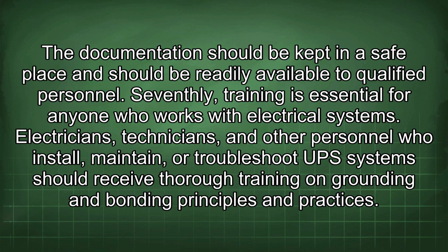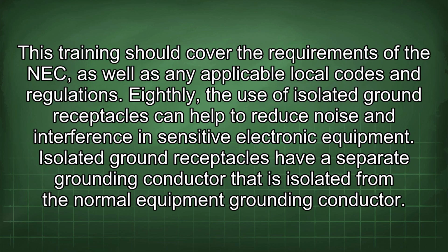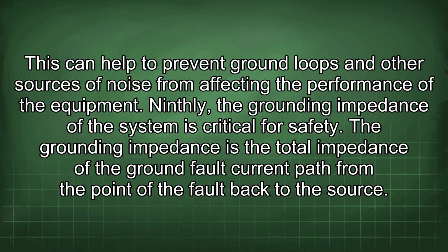The electricians, technicians, and other personnel who install, maintain, or troubleshoot UPS systems should receive thorough training on grounding and bonding principles and practices. This training should cover the requirements of the NEC as well as any applicable local codes and regulations. Eighthly, the use of isolated ground receptacles can help to reduce noise and interference in sensitive electronic equipment. Isolated ground receptacles have a separate grounding conductor that is isolated from the normal equipment grounding conductor. This can help to prevent ground loops and other sources of noise from affecting the performance of the equipment.